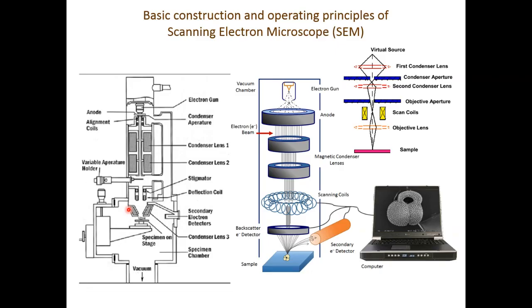This shows the basic construction of a scanning electron microscope. The top part is the electron gun where electrons are produced, then they are accelerated downwards through the column. The condenser lenses try to focus them into a narrow beam — the better the focus into a narrow beam, the better the resolution. Towards the bottom, the scanning coils help scan the focused electron beam across the entire surface or region of interest on the sample surface. The electromagnetic lenses make most of the difference — if they focus the beam to a very fine diameter or spot size, it gives very good resolution.